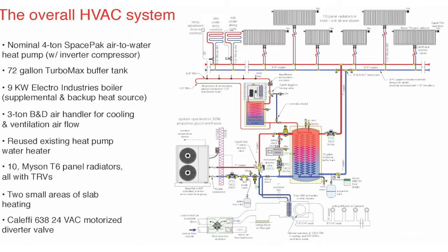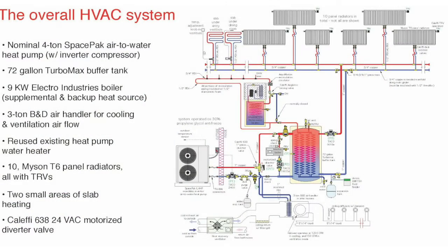Now, granted, the capacity and the COP is not really good at that point. I'd have to look up the COP, but I'm guessing maybe 1.2, something like that. It's still better than electric resistance heat. And the capacity is probably a third or less of its nominal capacity at those extreme temperatures. But you aren't at those extreme temperatures very often. In this location, it might hit minus 22 for an hour, maybe, in an average winter. So the machines can operate at low ambient.